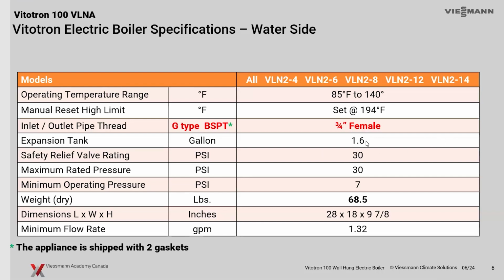But if you do want to add an expansion tank in the system, I think a couple of my drawings will show some recommended locations. Should you need to add one, we'll point that out. But the reality is that you can't really oversize your expansion tanks. You would just add more cost to your system. It does have one already included in there, and like I say, for 95% of the applications, that's going to be more than enough for you.